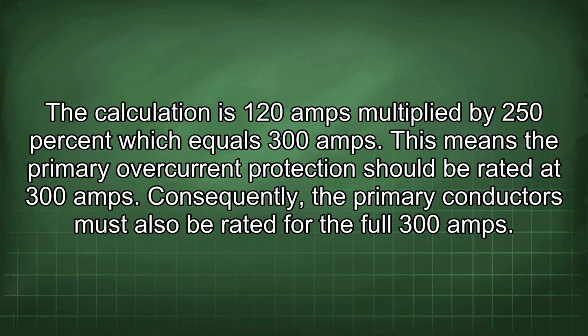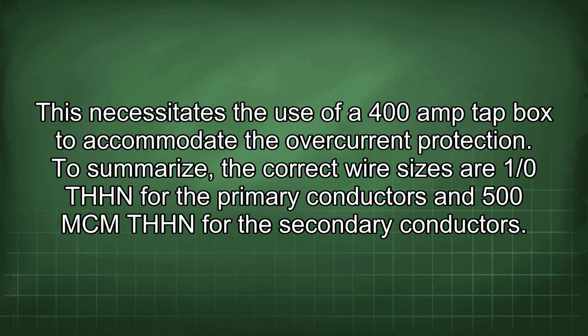The calculation is 120 amps multiplied by 250%, which equals 300 amps. This means the primary overcurrent protection should be rated at 300 amps. Consequently, the primary conductors must also be rated for the full 300 amps. This necessitates the use of a 400 amp tap box to accommodate the overcurrent protection.